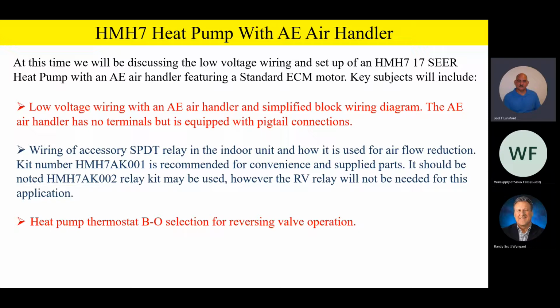So basically that 001 kit that we're talking about is going to have a biflow filter dryer in there. It's going to have some pre-made harnessing and then a relay on a board. And so that kit number 001 will be used for the standard ECM motor. However, it should be noted that the HMH7AK002 relay kit may be used as well. However, because there are 2 relays on that board, you will not use the RV relay if you use the 002 kit. So the 002 kit, you can use it on the standard ECM motor.